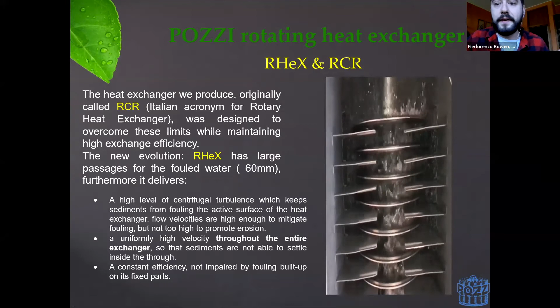Now, the second benefit of the turbulence is the fact that we are raising velocity. As I mentioned before already a number of times, the efficiency is directly proportional to the velocity that you're giving. So if you're raising the Reynolds number of the fluid, then you're raising efficiency. Another benefit is the fact that the centrifugal forces acting on the disc make it so that it is much more difficult for anything to get stuck to it.